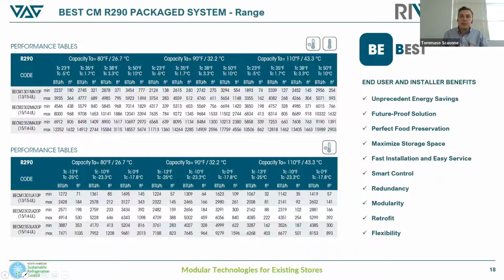Here I'm sharing the existing range that is basically built around 3 models for medium temp and 3 models for low temp, but with different voltages. The smallest models are 115 single phase 60 hertz, and all of the other models are 220 single phase 60 hertz, and the larger models are also 230 single phase 60 hertz. We build these models with multiple circuits, using 1, 2, and 3 circuits inside the same monoblock.